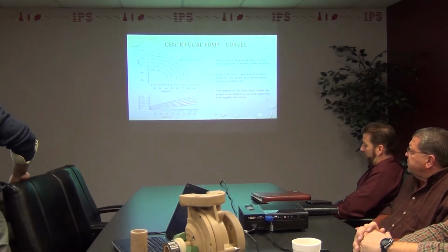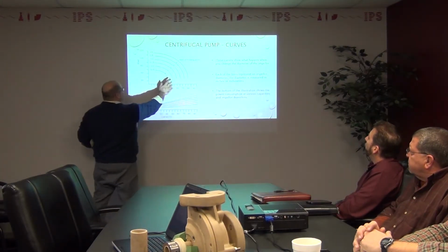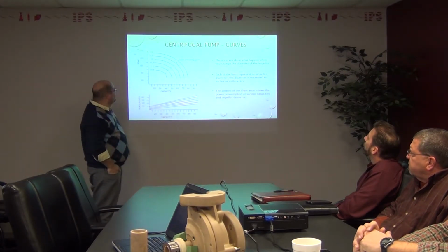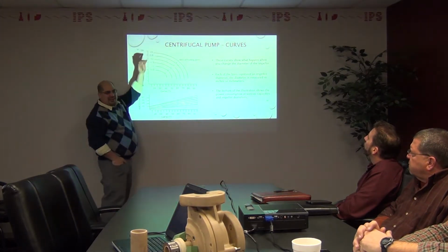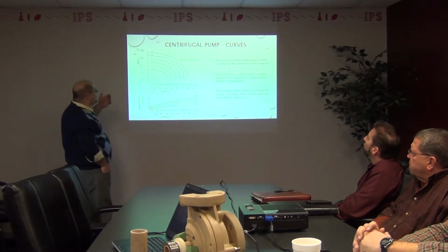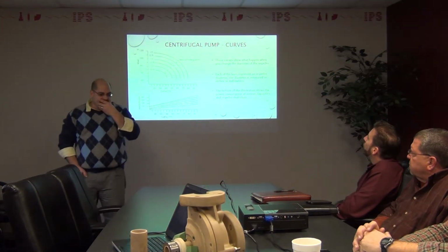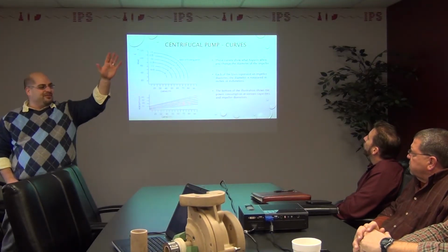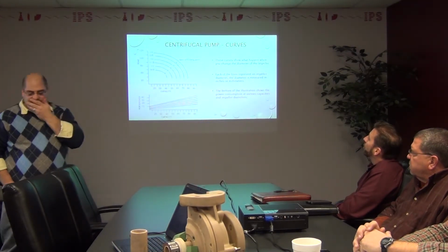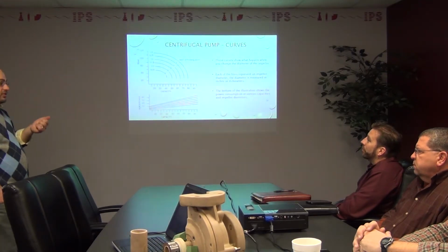So hey, we sized this pump for way out here, you know, the head pressure up here and whatnot. Okay, so we're shooting for the max, 115. But the customer really only needs 60. So theoretically, you think, hey, no problem, the pump can handle that because I can do 115. No, it doesn't work like that. Why doesn't it work like that?